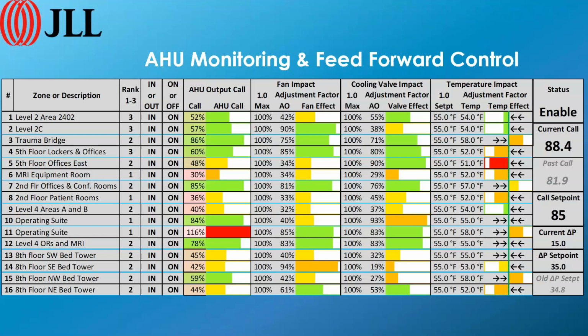So in essence, what we're doing is we're taking load information downstream from the information loop at the air handler, and we're using some of that information to, in advance, make adjustments to the delta P set point in the chilled water loop. So in other words, we're taking out some of that overshoot and undershoot.